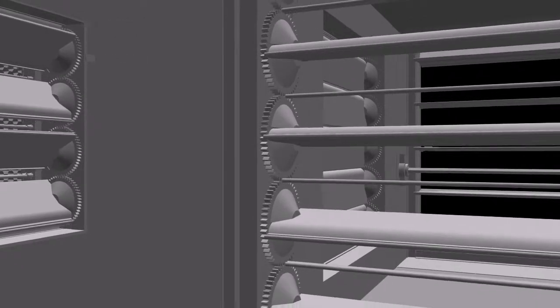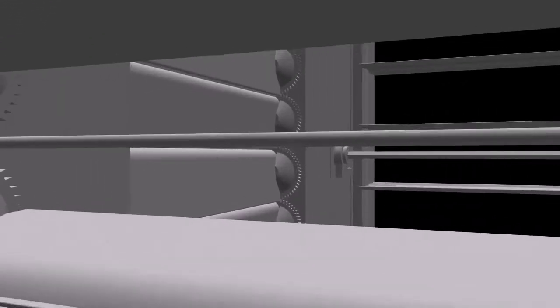A mixed air motorized damper that stops the return air being fed to the air handler during free cooling. And lastly, a return air fire smoke damper that responds to inputs from the engineered smoke control system in case of fire. The air handler unit receives a run command.